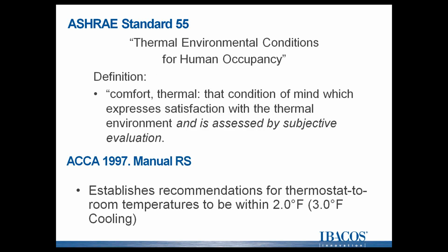What we like to use often is ACCA Manual RS as a rough guideline for establishing comfort, and the definition is that all of the rooms should be within 2 degrees Fahrenheit of the thermostat during the heating season and 3 degrees Fahrenheit during the cooling season. A homeowner can set their thermostat to whatever they feel is comfortable, and they should expect their entire house to have a uniform level of comfort.